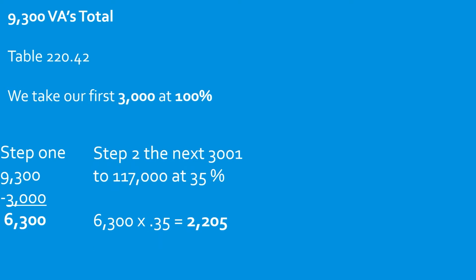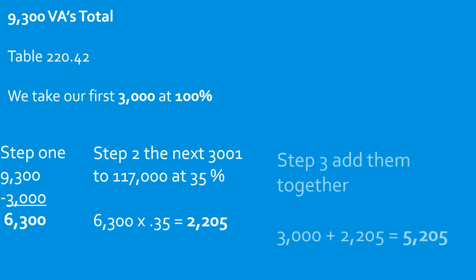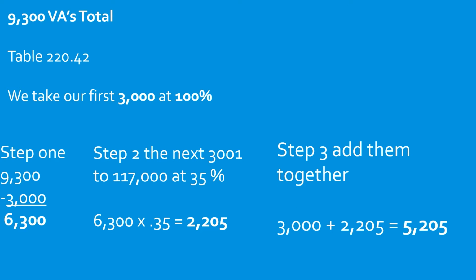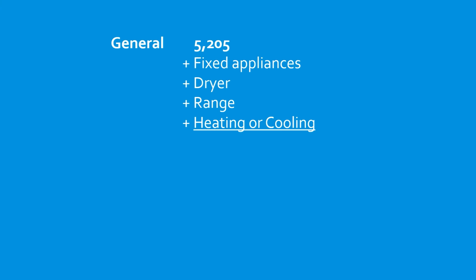In the next step, you're going to take the next portion and multiply it and get 35% of it. So you take 6,300 multiplied by 0.35, and that is going to give you 2,205 VAs. Then all you have to do in step 3 is add the 3,000 that you set to the side to the reduced load, and now you have 5,205 VAs. Now you go ahead and put that at the top of your calculation. If you structure your question like this, you'll be able to move down as you go, and you'll see what I do here.